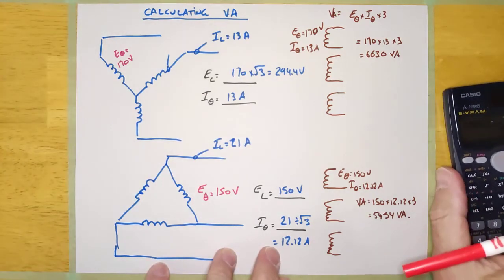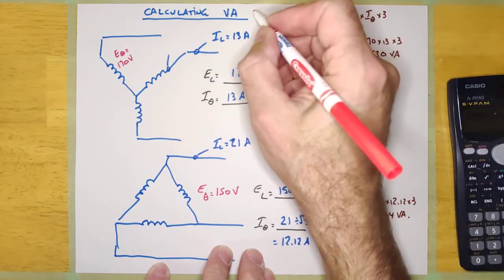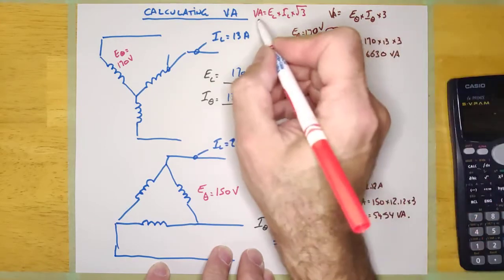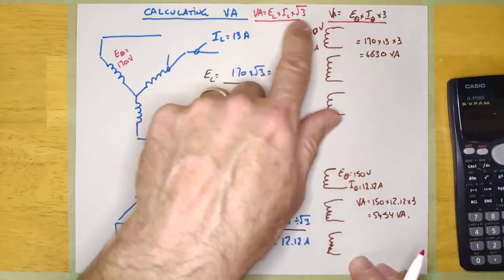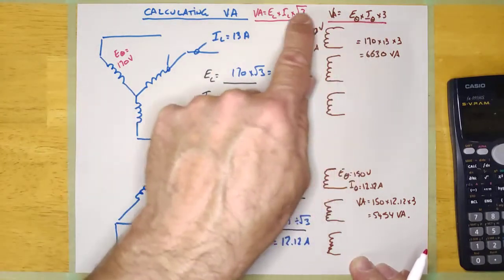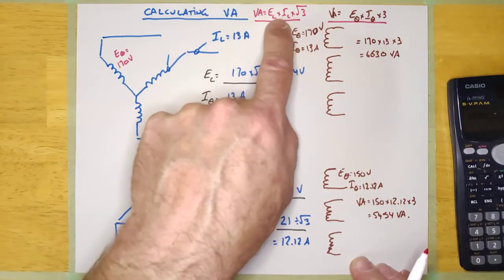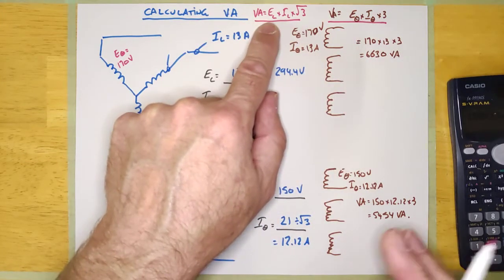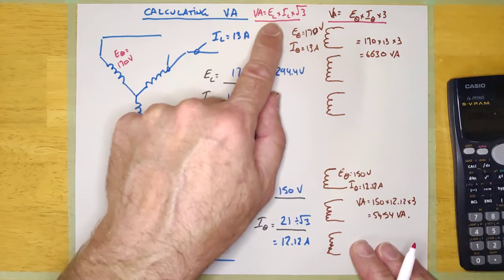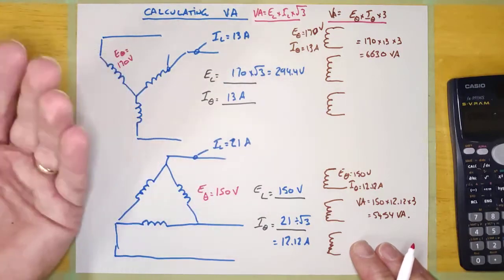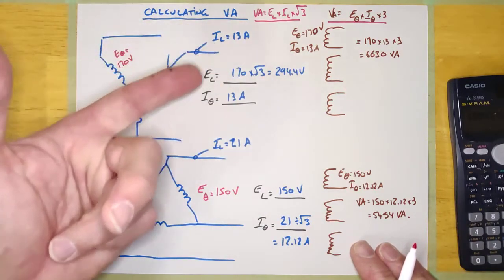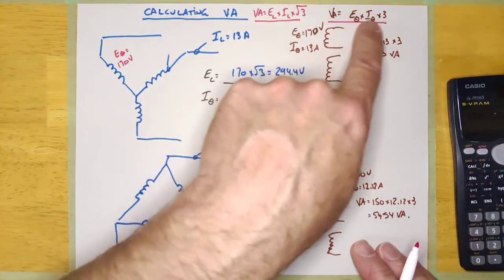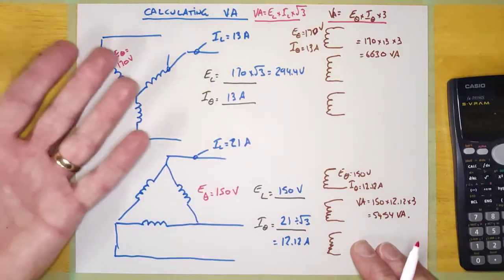There's an alternate formula which you might find handier: VA = E_line × I_line × root 3. Those two formulas will always allow you to calculate the VA for any three-phase transformer. This second one is usually easier because electricians most often know the line voltage and line current — a transformer nameplate will show line voltages and line current, and you don't even need to know whether it's wired Y or Delta.